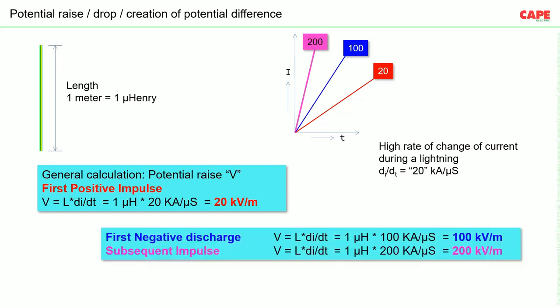Similarly, if we calculate for first negative impulse and subsequent impulse, V is equal to L di/dt. L is 1 microhenry. Di/dt in case of negative impulse was 100 kA per microsecond, and in case of subsequent impulse was 200 kA per microsecond. So voltage drop comes around 100 kV per meter and 200 kV per meter. That means whatever good quality SPD we are using, with 1 meter of wire, the voltage drop will be around 100 kV per meter.